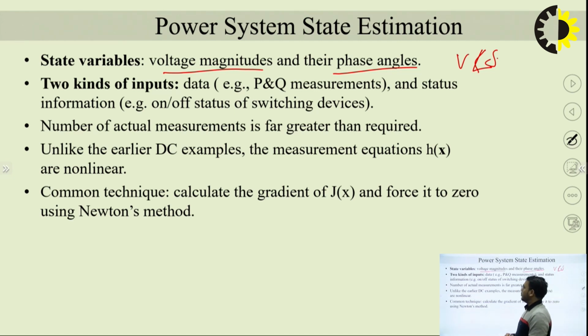We have two kinds of input. The first is data, which is the value of real power and reactive power, so P and Q measurements are the two kinds of input data to the system. The second is status information, basically the position of circuit breakers, isolators, and on/off conditions of switching devices. If a switching device is on, you assign value 1; if off, value 0.